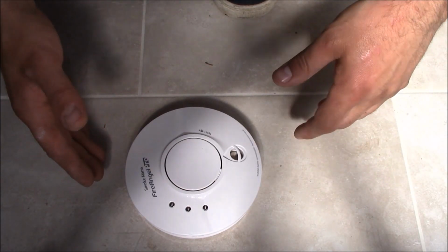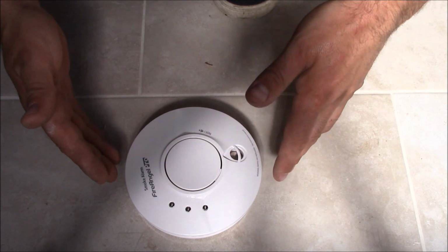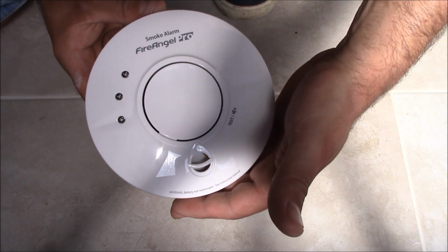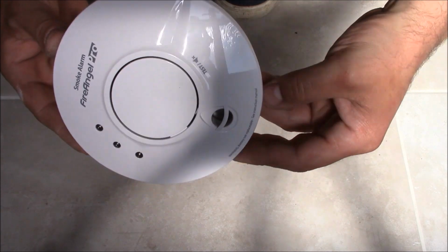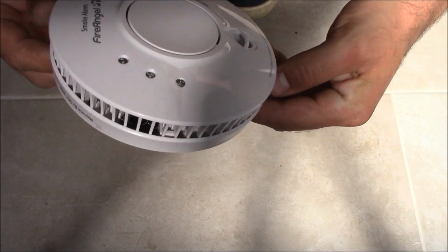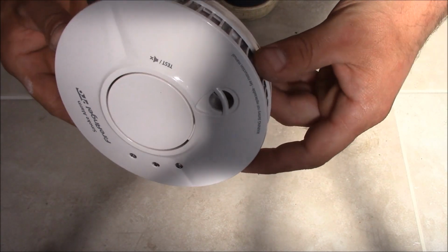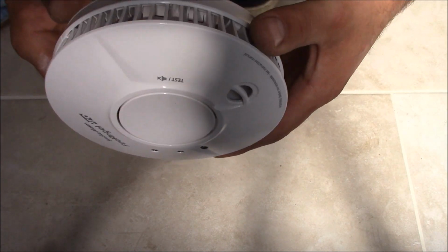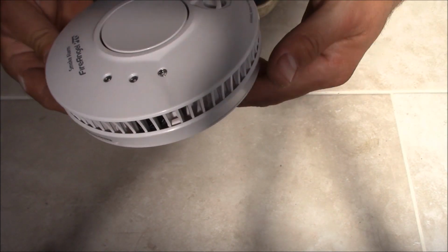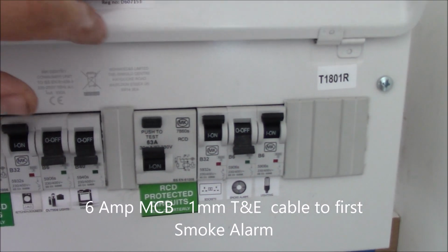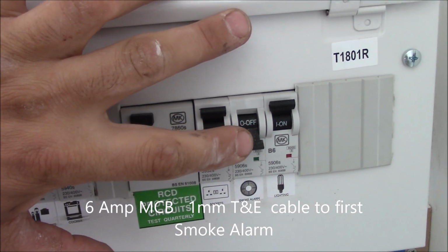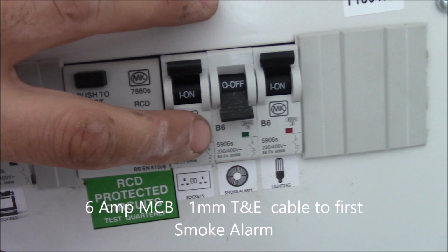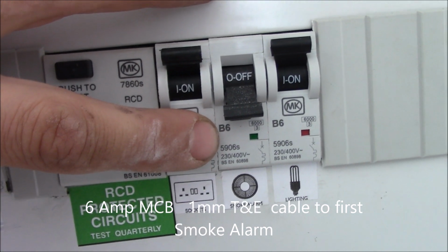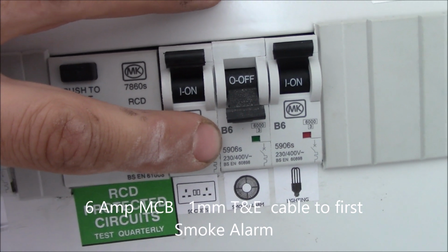In this video I'd like to show you how to install the smoke alarm. Basically this one is a Fire Angel Pro, a smoke alarm. So I'm going to show you how to install it onto the ceiling, how to wire it and interconnect it with another smoke alarm. The consumer unit, as you see, the smoke alarm's got its own dedicated circuit and it's on the 6 amp circuit breaker.